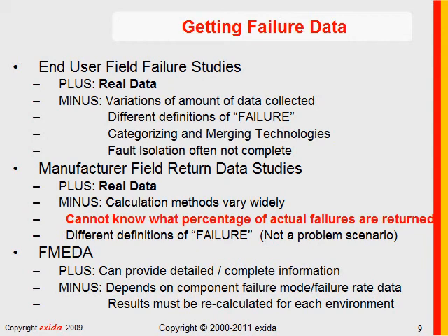I can also get failure rate data from manufacturers' field return studies. And it's real data as well, and that's a plus we cannot ignore. However, I will tell you that when I worked for a manufacturer, I was taught by the quality department to look at shipping records. And I was taught to assume that 2 weeks after a product was shipped, it was put into service. Then I could start counting operational hours.